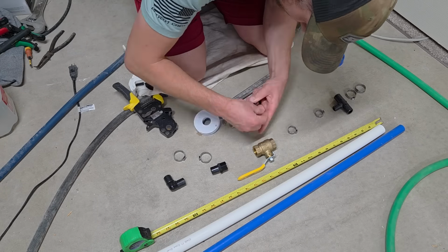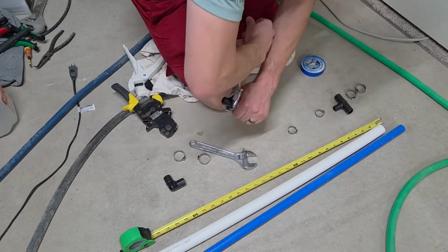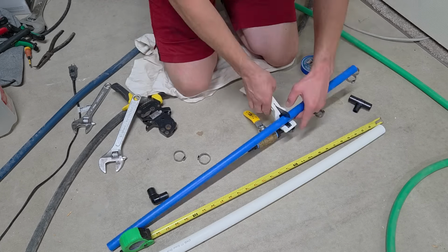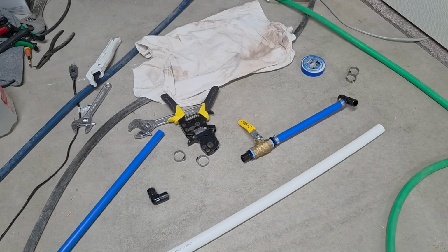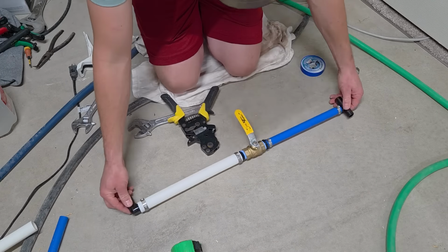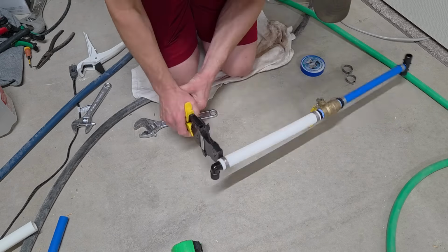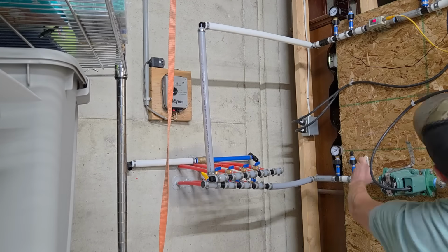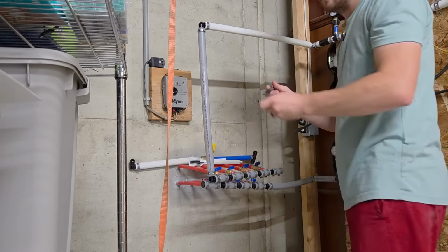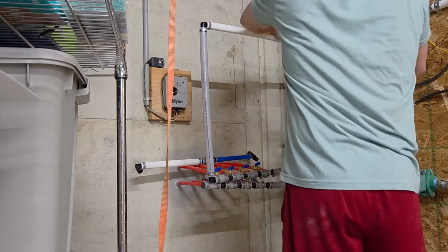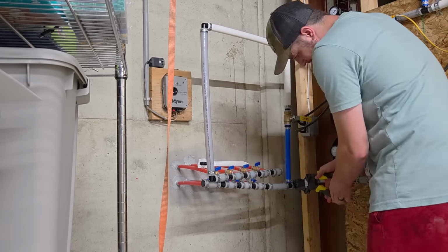So halfway through this test, I figured it's easy enough to modify the plumbing to bypass the ground loops so that I can run the coldest water possible through the heat exchanger. So that's what I'm doing here. I had to pick up a few plumbing components, cut into the closed loop system, add a bypass and a couple valves, burp all the air out of the system, and then we're back in business to see how much colder the water is if it doesn't have to go through the ground loops.